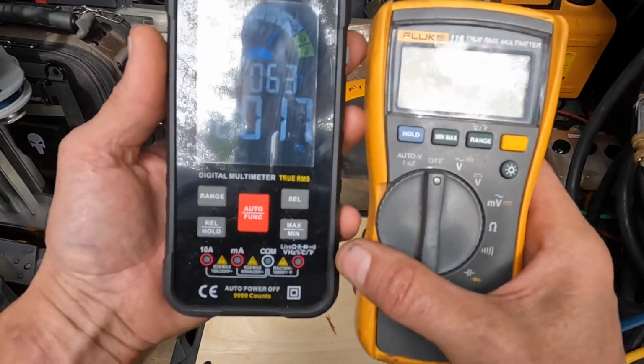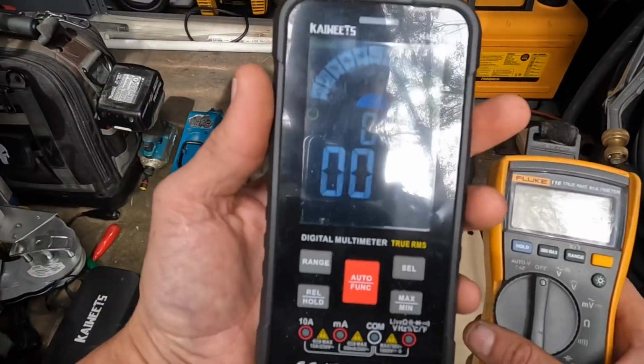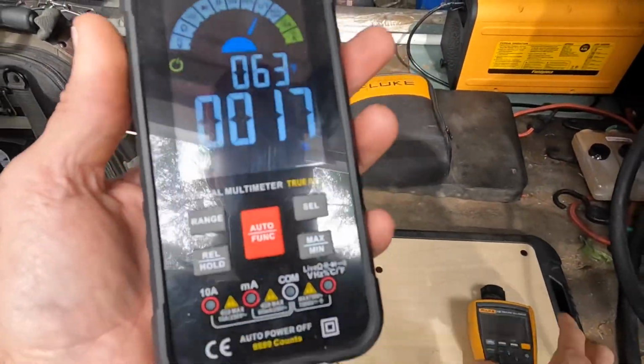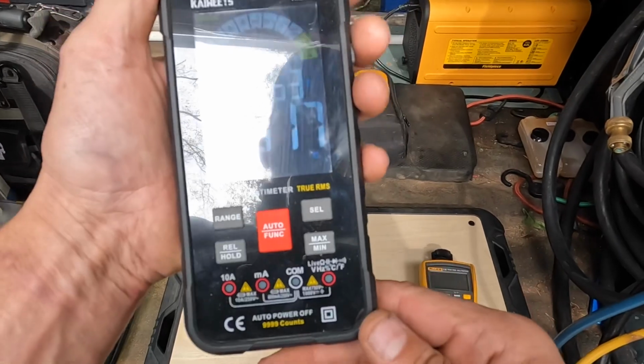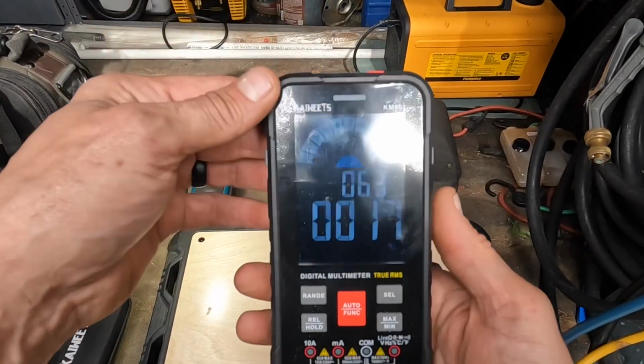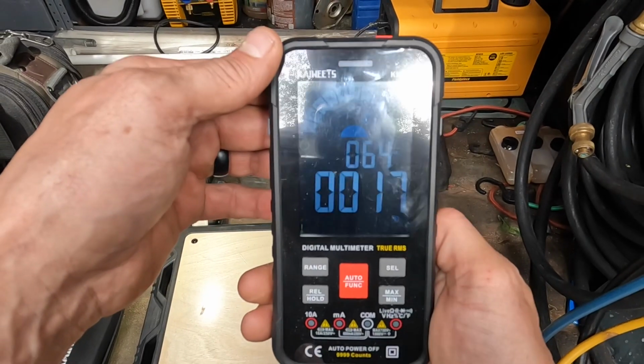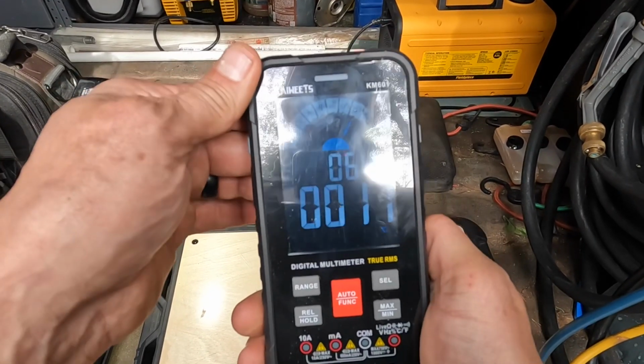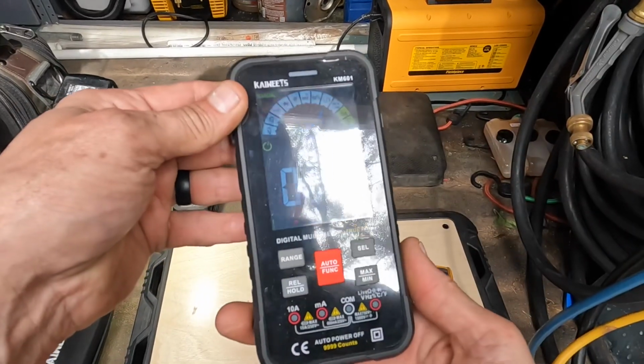This is a true RMS meter, but I did not see in the paperwork anywhere where it said Cat 3 or Cat 4. The paperwork does say it's rated up to 750 volts, so I think that would be like a Cat 3, but it has no Cat rating on it at all.